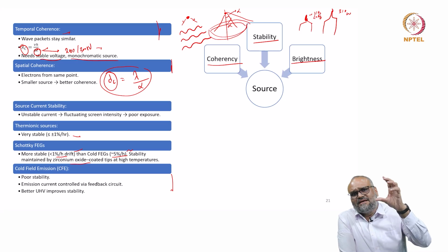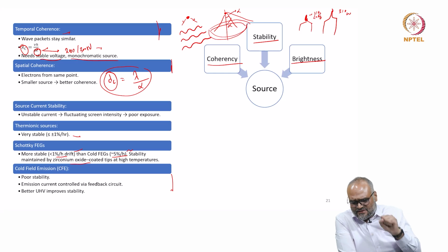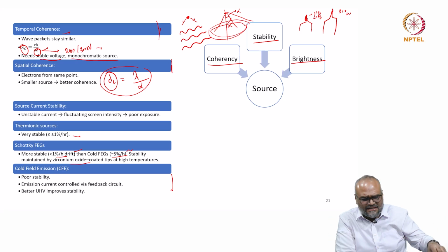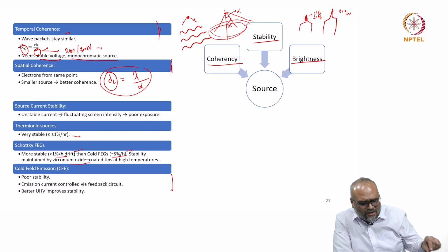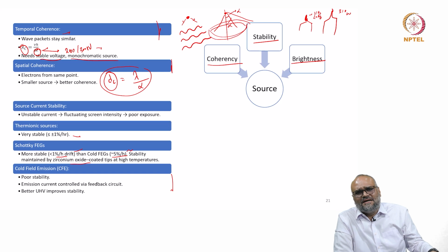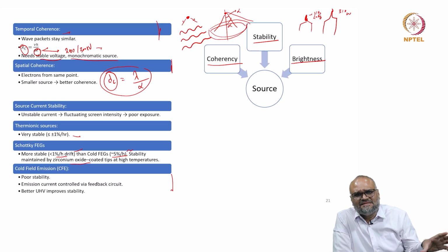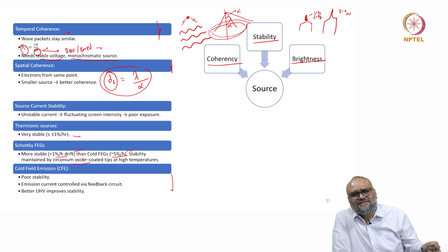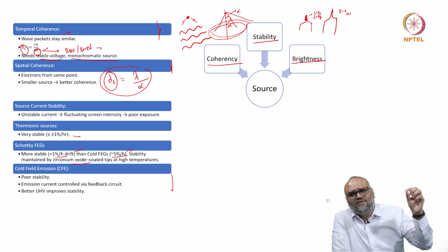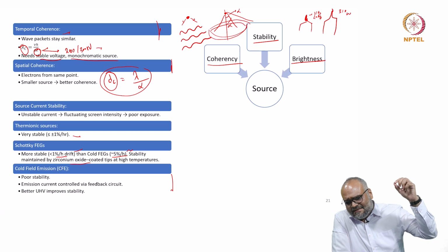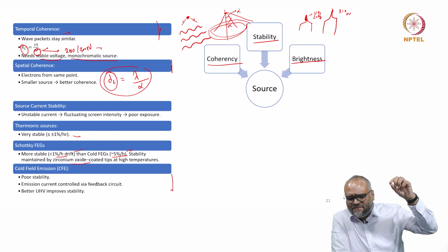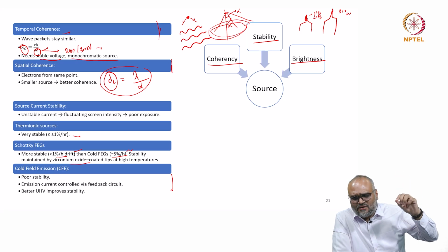Once it goes through the condenser and the illumination system of the microscope, I can naturally converge the beam to a point or spread it by turning the intensity or the brightness knob. Although it is written as the brightness knob on the microscope console, you are not actually changing the brightness, but you are changing the intensity of the electrons that are spread over an area. By changing the spot size, what I am doing is I am changing the size of the crossover point at the condenser lens, or the first crossover that is formed beyond the emitter.